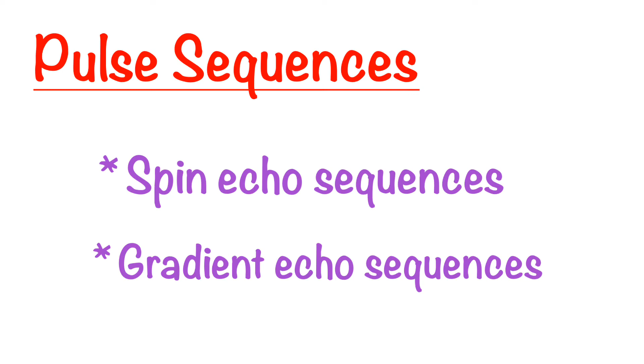To measure the relaxation time and produce an image with good contrast, we need to regenerate the signal, and there are two ways of doing this. The first one is by using an additional 180-degree RF pulse, and it's called spin echo pulse sequences, and the second one is by using gradients, and it is called gradient echo pulse sequences. Let's have a look at the steps of the applied sequences in spin echo.